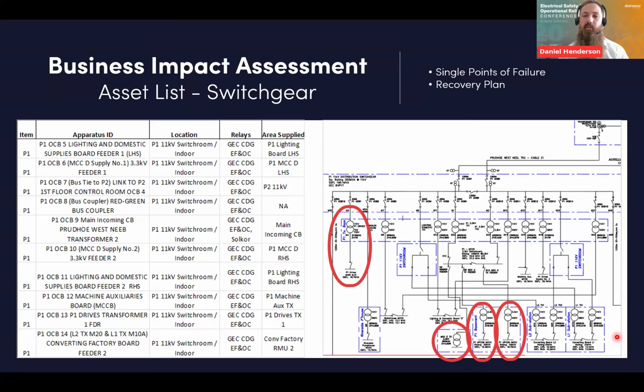And that's why in the planning, they've been built with N+1 capability. So in the event of losing a circuit breaker, cable, transformer, even the full side of the board, or taking those off from a maintenance perspective, you've got that N+1 redundancy built in so that you can keep those assets going, or in the event of a fault, hopefully recover those assets by bus coupling and getting them recovered in a short period of time as part of your recovery plan.